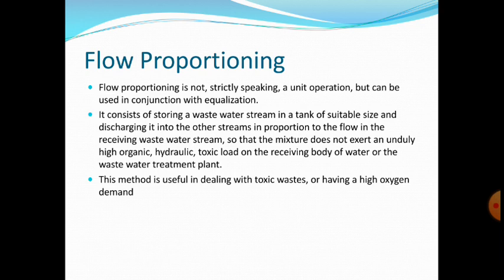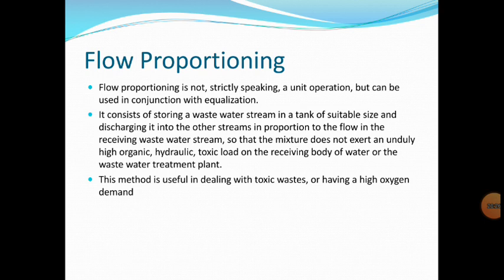Next comes flow proportioning. Flow proportioning is not strictly speaking a unit operation but can be used in conjunction with equalization. It consists of storing a wastewater stream in a tank of suitable size and discharging it into other streams — either domestic sewage or industrial waste — in proportion to the flow in the receiving wastewater stream, so that the mixture does not exert an unduly high organic, hydraulic, or toxic load on the receiving body of water or the wastewater treatment plant.